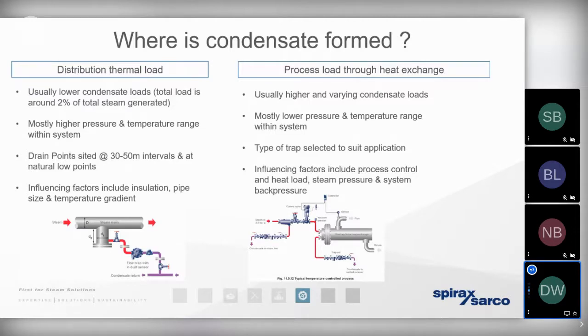And of course, the remainder of the steam is going to give up its heat energy at the process. And as we've mentioned, that's a good thing because that's where we want the steam to condense and give up its heat energy. But just as we apply a warming up load for the steam traps on the distribution pipework, it's good working practice to allow a similar warming up load at the process.